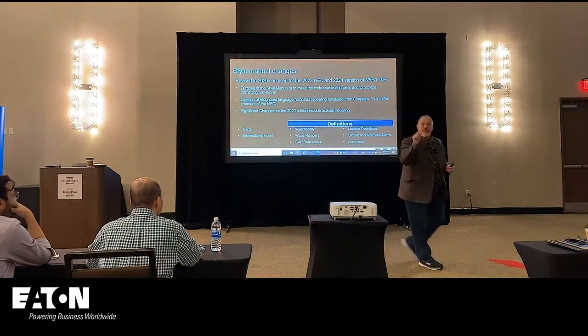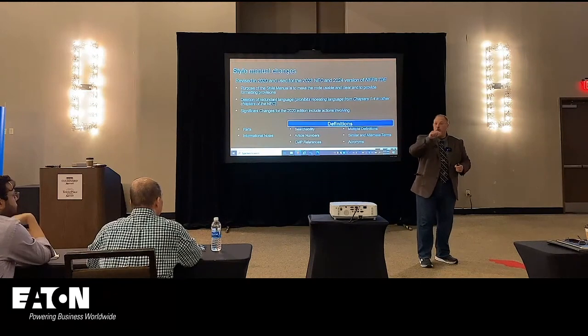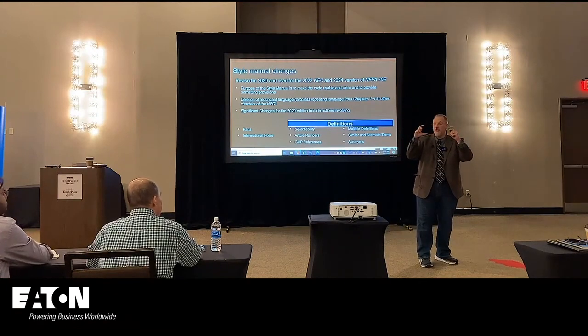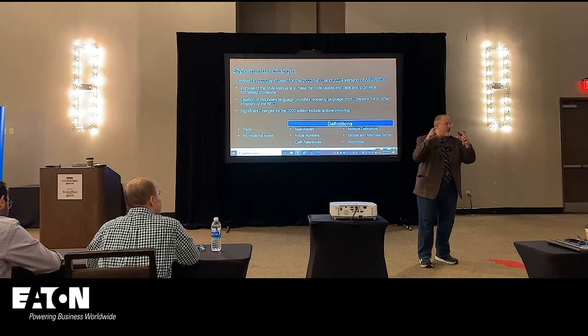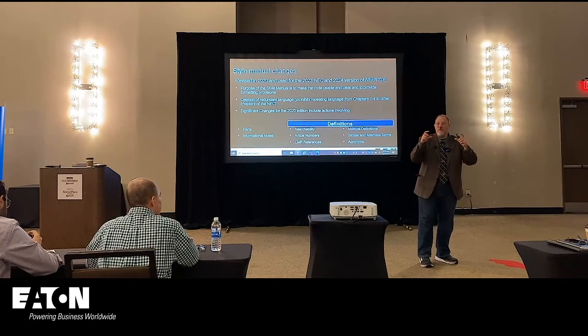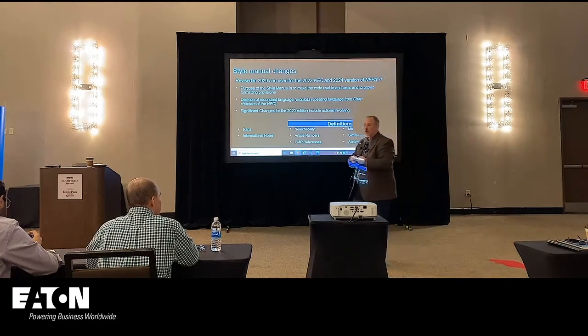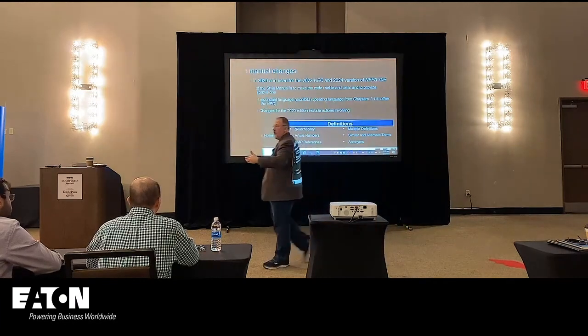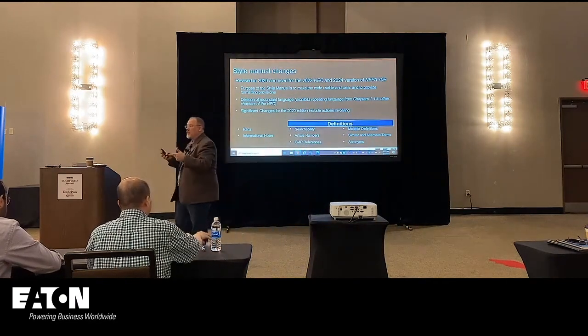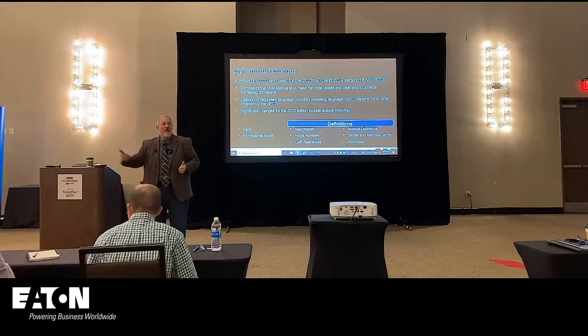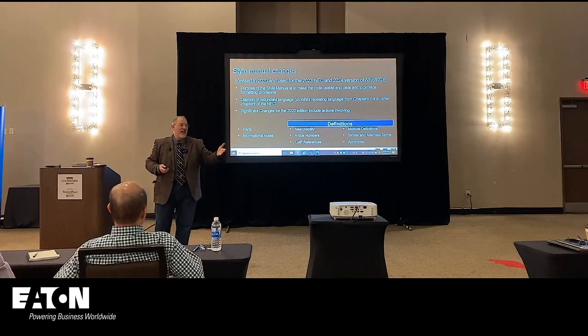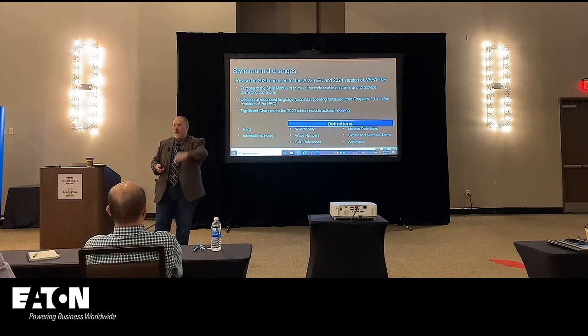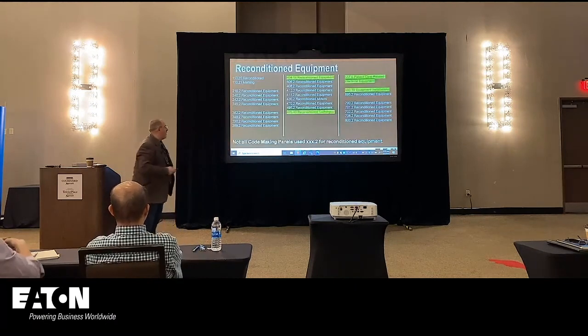And if you're looking that term up, and you see that extracted text, and you see another NFPA document, I would ask you to go look at that document, because if you're reading something and trying to apply the code in an application where you're seeing extracted text from another document, there's a very good chance that the requirements in that other document apply to whatever it is that you're working on. So be mindful of that.